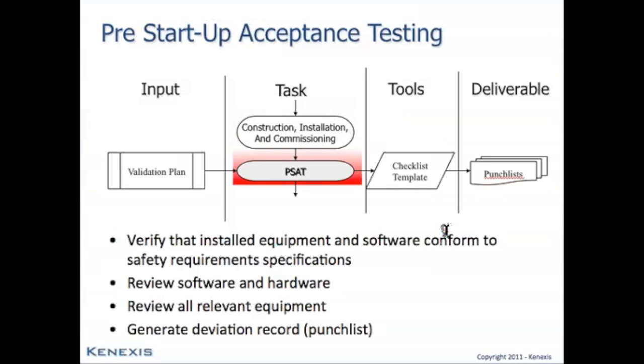After the commissioning phase is complete and the instrumentation and control contractors are ready to turn the system over to the operating company for operations, a pre-startup acceptance test, or in the terminology of the IEC 61511 standard, a validation needs to be performed. During this task, we're going to verify that all of the installed equipment and all of the software conform not to the detailed design documents, but to the FGS requirement specification or the safety requirement specification. This is to ensure that errors were not generated in the detailed design documents, and if they were, they can be caught prior to the startup.